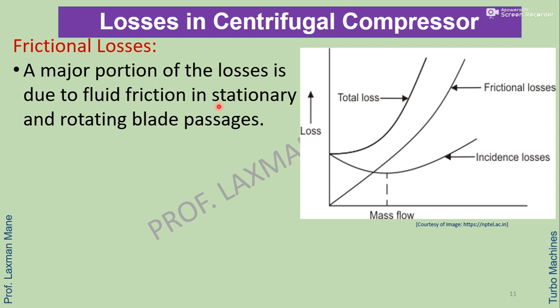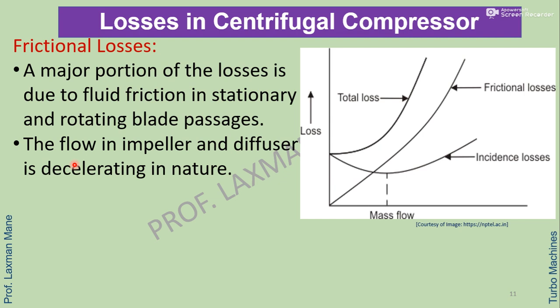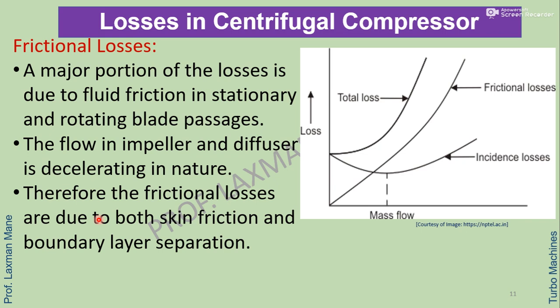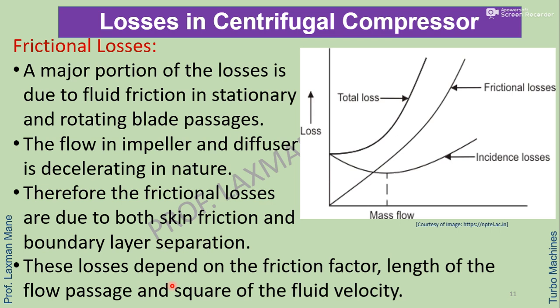Losses in centrifugal compressor: on the diagram, the vertical axis shows losses and the horizontal axis shows mass flow rate. There are three curves: frictional losses, incidence losses, and total loss. Frictional losses form a major portion, due to friction in stationary and rotating blade passages. The flow in the impeller and diffuser is decelerating, so frictional losses arise from skin friction and boundary layer separation. These losses depend on friction factor, length of flow passage, and the square of flow velocity.